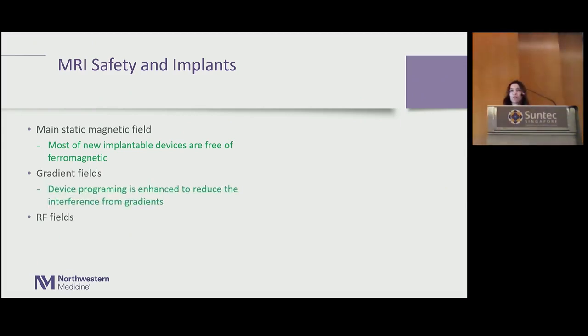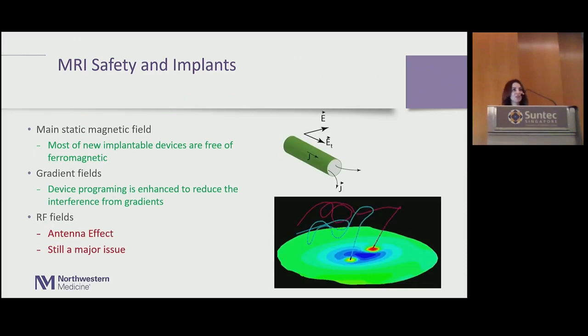Gradient fields used to be really problematic, specifically for cardiac implants, because they would interfere with the device. They would make your pacemaker pace the heart at a rhythm that it shouldn't, so it could induce arrhythmia, which could be fatal. Not anymore. We have much better technology, safeguard switches that put these devices in MR mode, which basically takes care of that interference problem that caused the device to malfunction. What remains as a nuisance is the RF field that produces the heating.